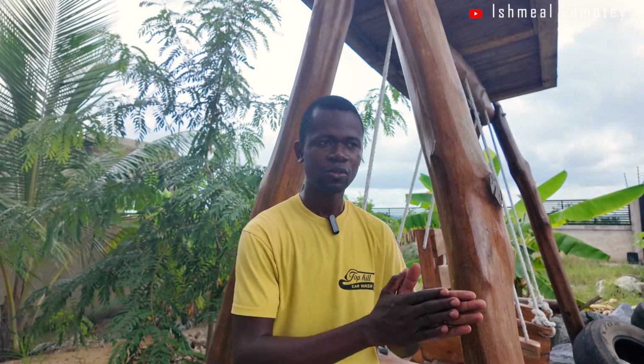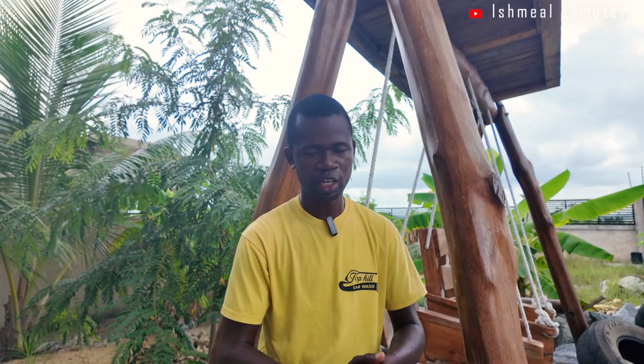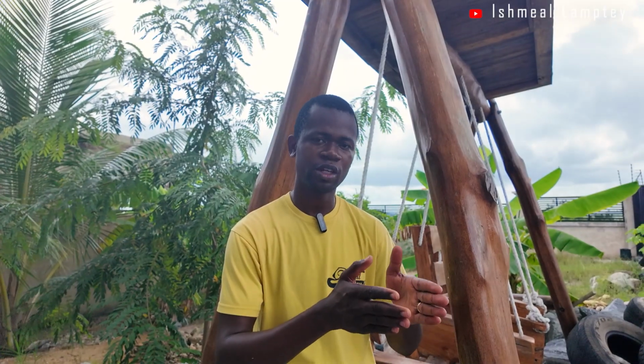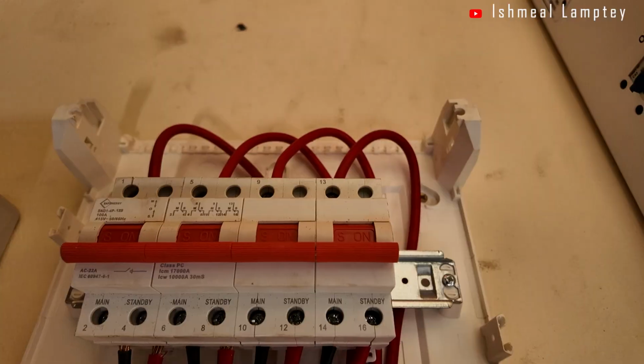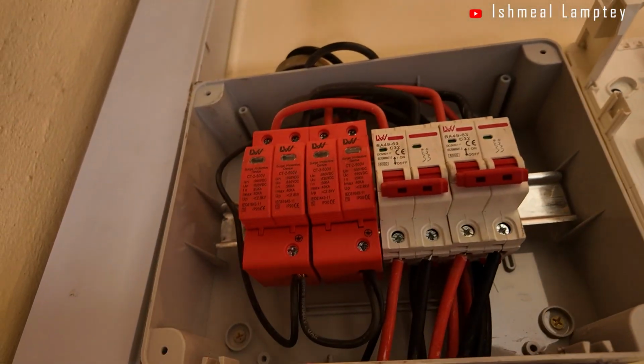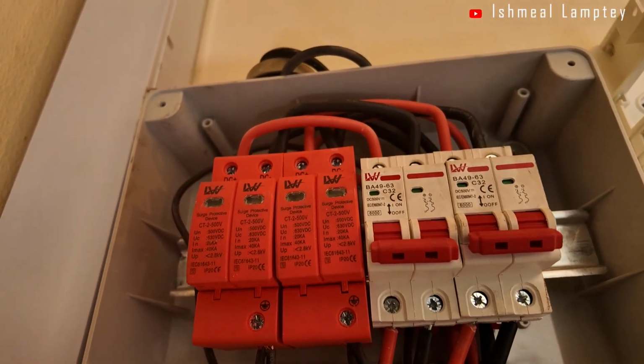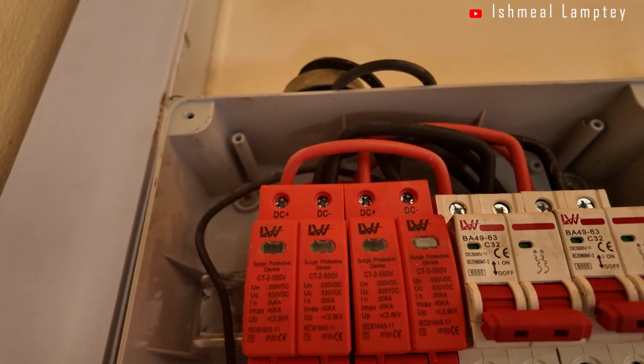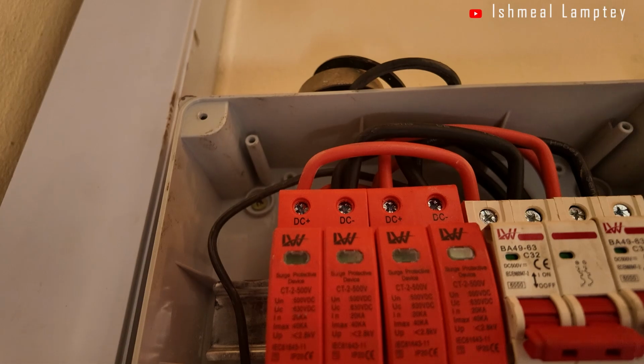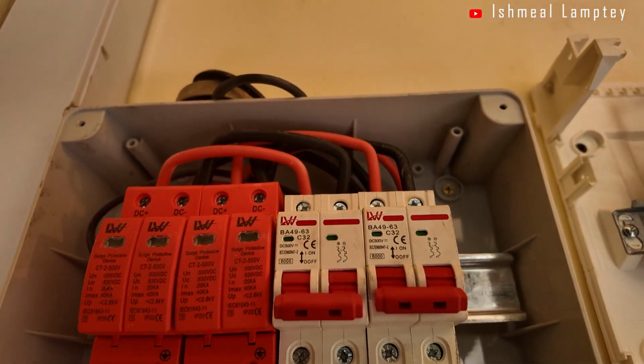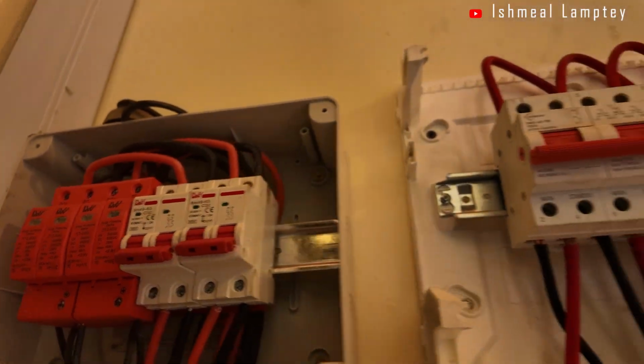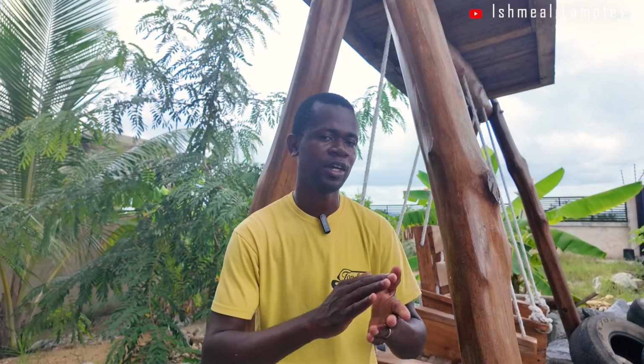For the panels, after mounting them, 6 each in series, and passing all the cables to where they were going to go, we installed breakers for them. We used 32 amp breakers for each panel string, so that was 2 pieces, and then we also used 2 pieces of SPD. The purpose of the SPD is to channel any excessive power coming through the system to the earthing system. As part of the configuration of the SPD, there's earth to earth. So you connect earth cables so that in case any excessive power is generated from the panels through lightning or anything, that excessive power is channeled to the earth. So that was a layer, or different layers, of protection we applied to the panels: 2 breakers and 2 SPDs.